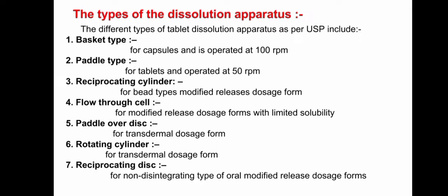3. Reciprocating cylinder for bead types of modified release dosage forms. 4. Flow-through cell for modified release dosage forms with limited solubility. 5. Paddle over disc for transdermal dosage forms. 6. Rotating cylinder for transdermal dosage forms. 7. Reciprocating disc for non-disintegrating type of modified release dosage forms.